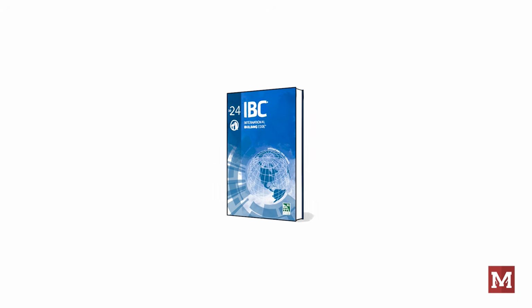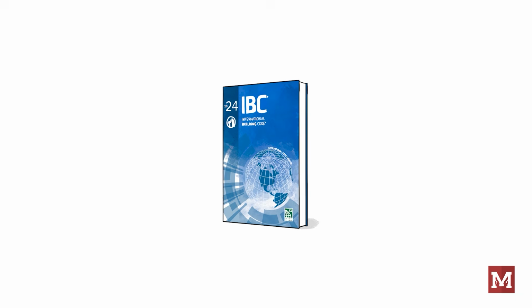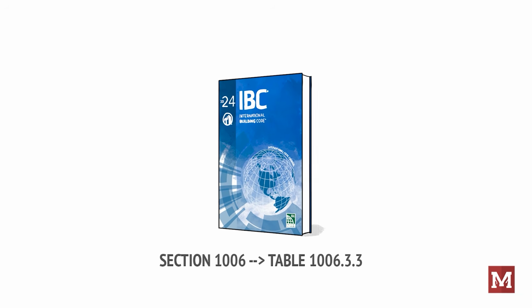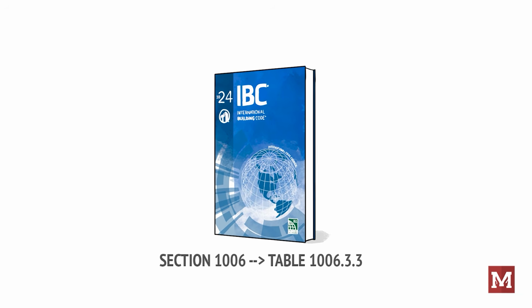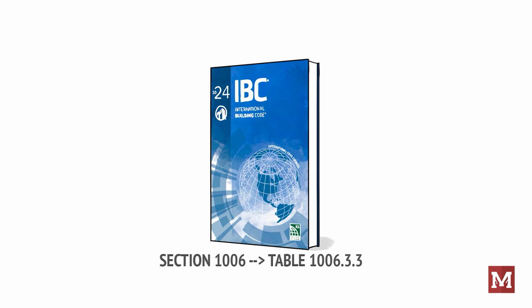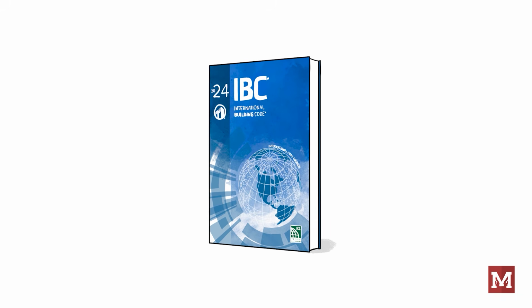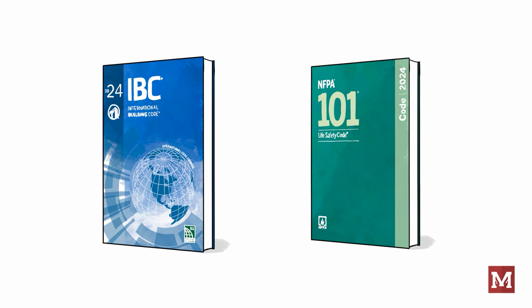In the IBC, we'll find this by going to Chapter 10, then Section 1006, subsection 1006.3.3, and finally, Table 1006.3.3. In NFPA 101, we find this by going to Chapter 7, then Section 7.4, subsection 7.4.1, and finally, Section 7.4.1.1 and 7.4.1.2.